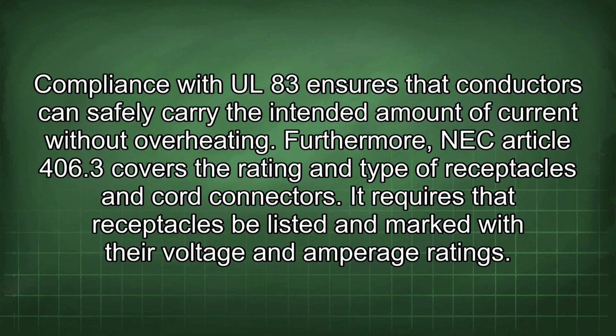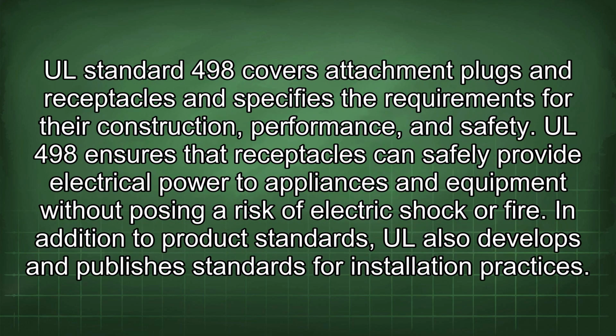Furthermore, NEC Article 406.3 covers the rating and type of receptacles and cord connectors. It requires that receptacles be listed and marked with their voltage and amperage ratings. UL Standard 498 covers attachment plugs and receptacles and specifies the requirements for their construction, performance, and safety.